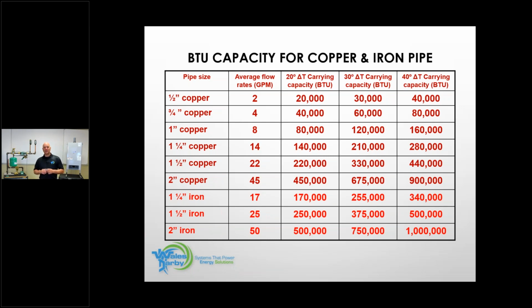We find the most common header size off of a boiler is 1.25 inch, and if that is the case, and you install a 200,000 BTU boiler, you can see here at a 20-degree delta, 1.25 inch pipe carries 140. That becomes your roadblock of getting the heat out of the boiler. And if you are short cycling that 200,000 BTU boiler, this may explain why.